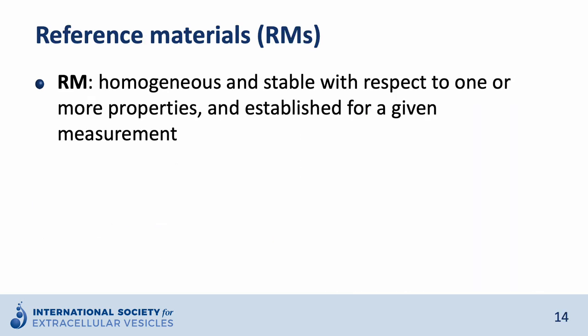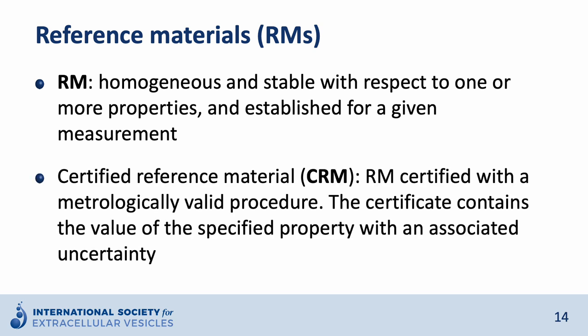The last term I would like to introduce is the reference material. A reference material is homogeneous and stable with respect to one or more properties and established for a given measurement. Different levels of reference materials exist. For example, there are certified reference materials, or CRMs. These CRMs are certified with a metrologically valid procedure, and the certificate contains the value of the specified property with an associated uncertainty. CRMs represent the highest level of reference material.